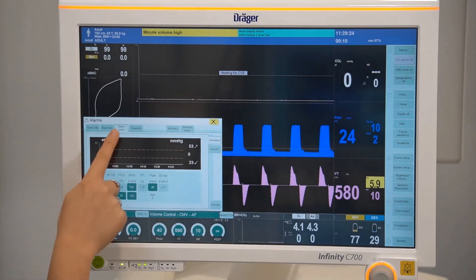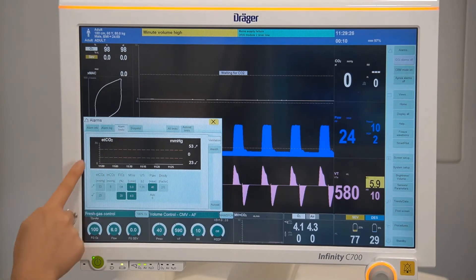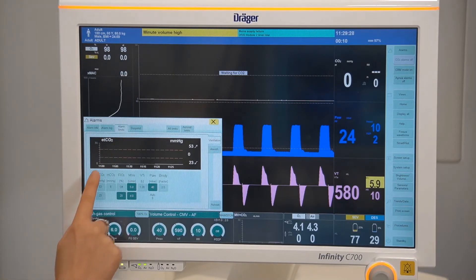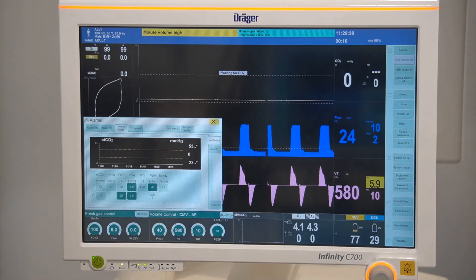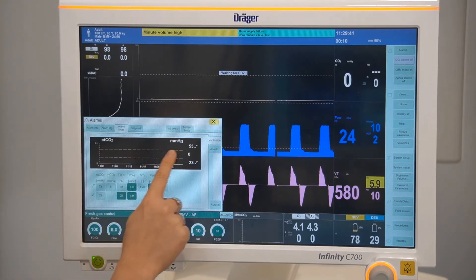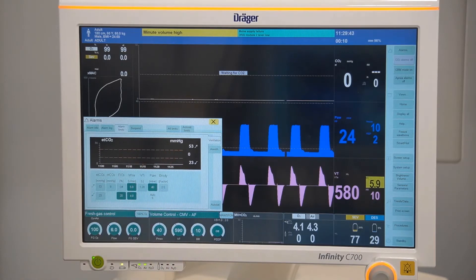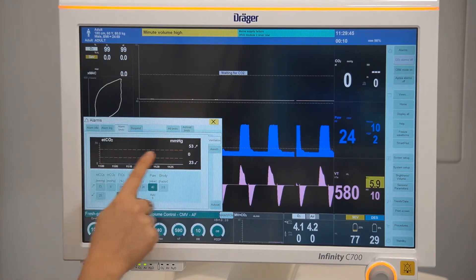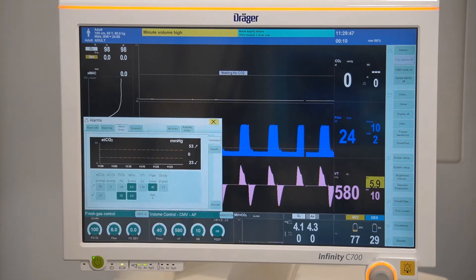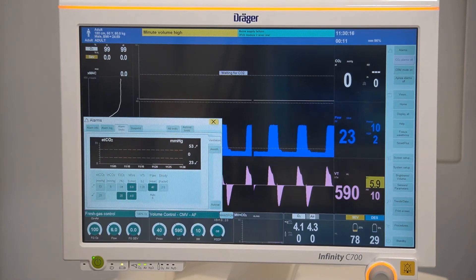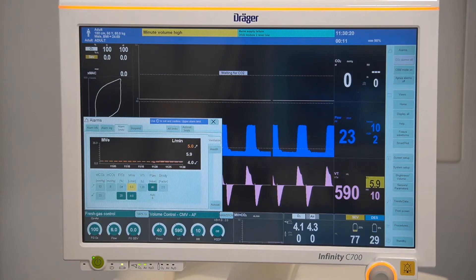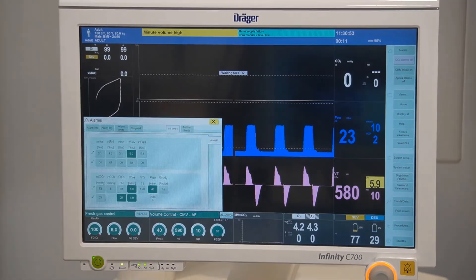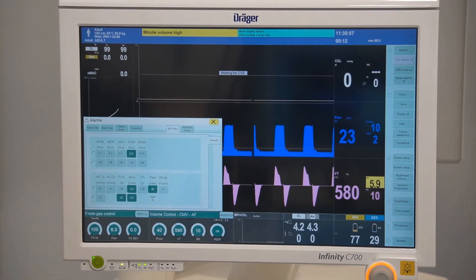The alarm limits will display the relevant parameter and the 30-minute trend of that parameter. The orange dotted line represents the alarm limits, and in this instance there is an upper and a lower limit. By touching on another parameter, information specific to that will be displayed. All limits displays all your parameter alarms.